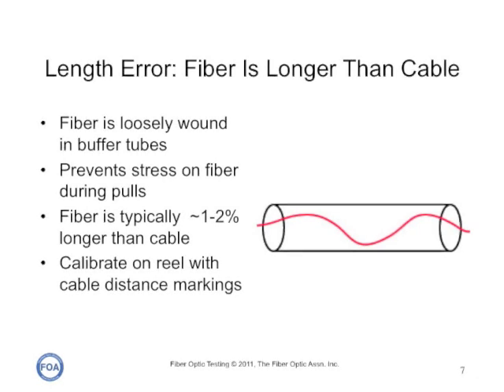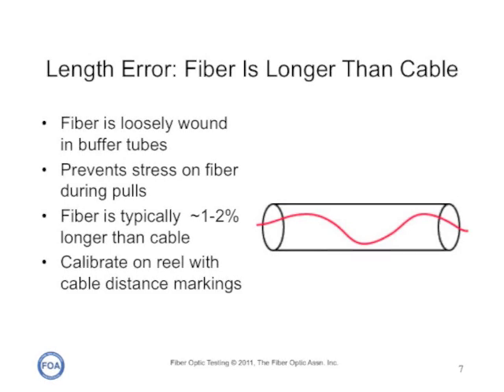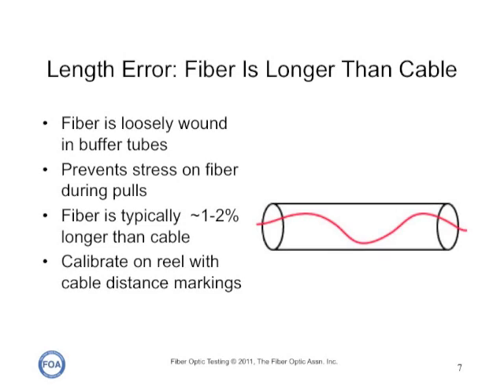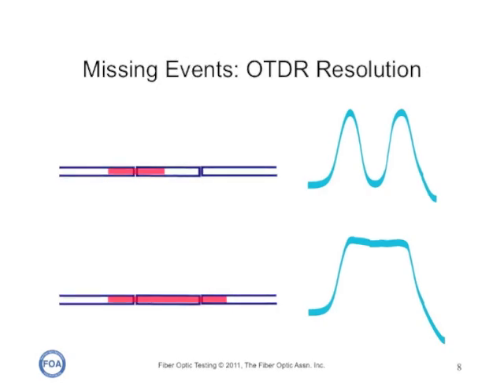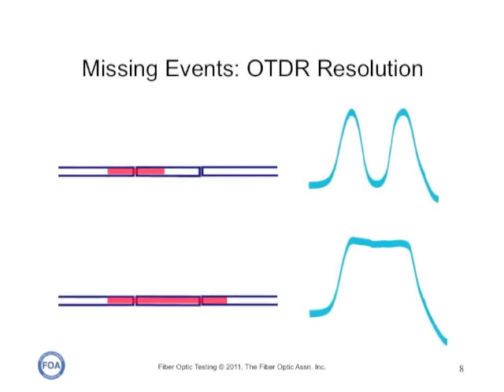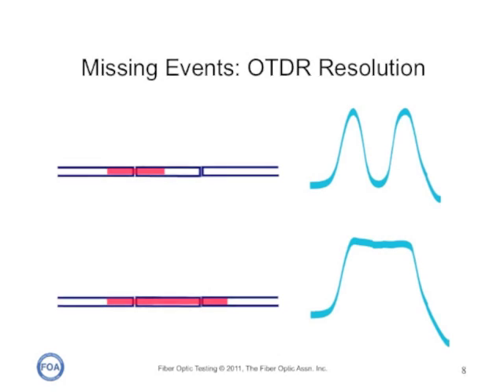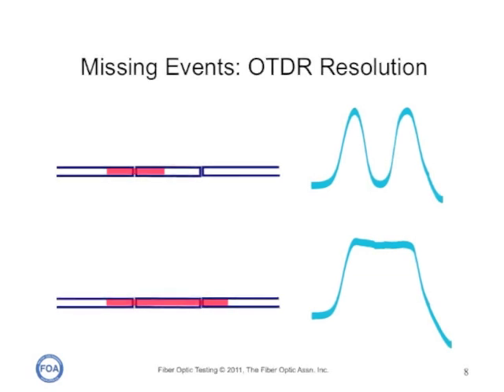That means that if you measure 10 kilometers, the actual length is going to be less two percent. So if you're trying to find a break in a fiber, you always look before the distance that the OTDR tells you, because that's where the actual cable length will be. The OTDR can completely miss some events if they're close together. Because the OTDR pulse width is variable, that distance can change. But if you have two events that are close together and a wide pulse width, they will be completely lost. Thus, you have to be careful to always try to use the shortest possible pulse to get the best possible resolution.